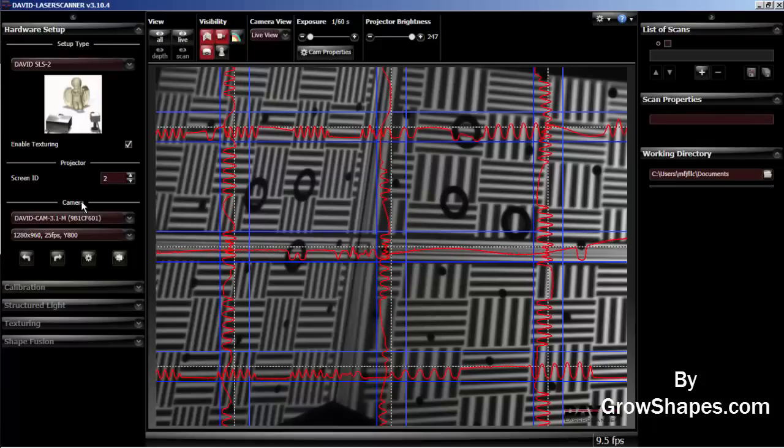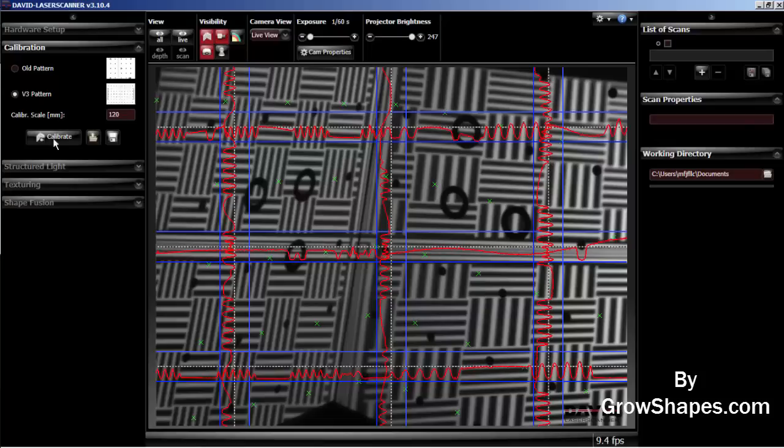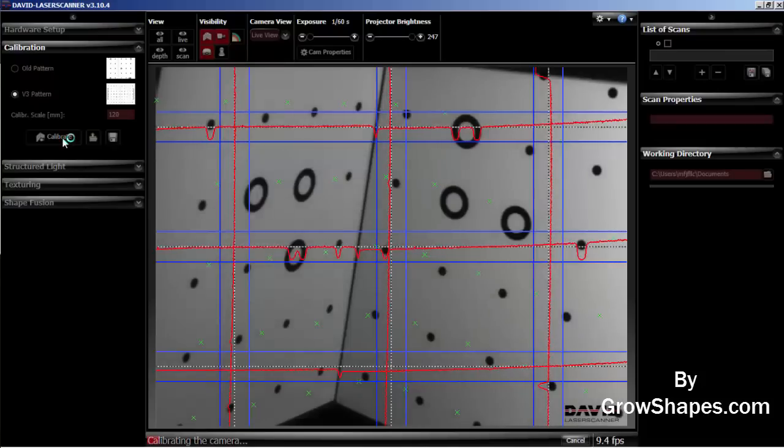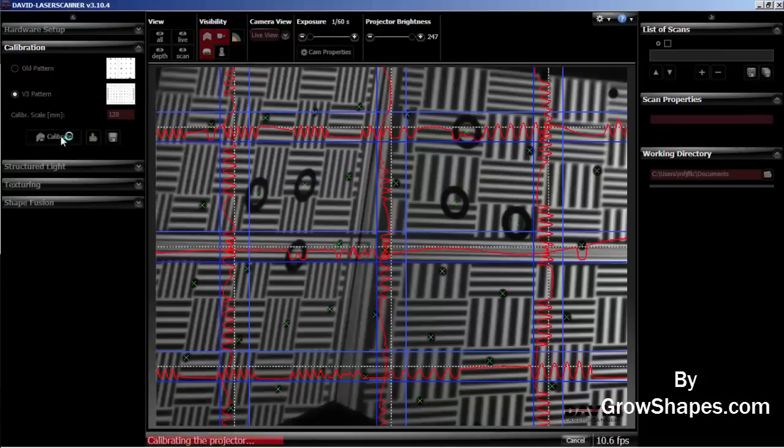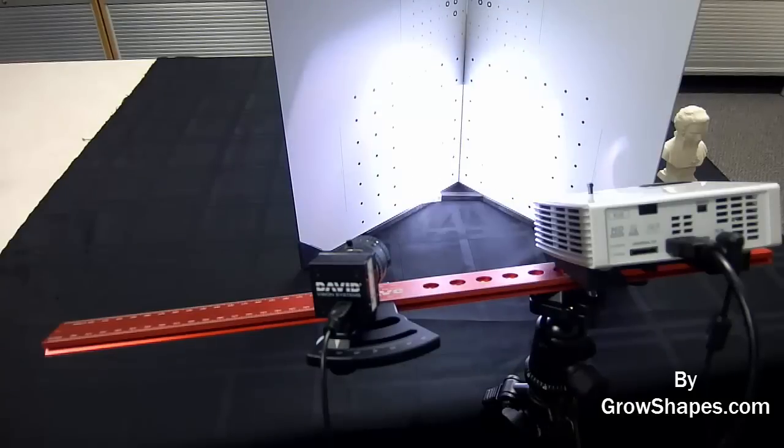Now you are ready to calibrate. Go to the calibration menu on the left side of the screen. Make sure you enter the correct calibration scale length. In my case, it is 120 mm calibration scale length. Hit the calibration button.